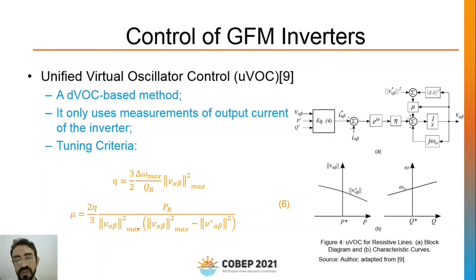We have 3 control gains to define in this control, which are mu, the voltage error gain, eta, the current error gain, and phi, which is defined as the equivalent impedance as seen from the point of coupling of the inverter. At steady state, this control presents this droop relationship, which is nonlinear for active power droop, and linear for reactive power droop, but has a coupling with the voltage. The tuning criteria for this control is also based on steady-state operation points, where the eta gain is defined as a function of the maximum frequency deviation, the maximum voltage deviation, and the rated reactive power. The mu gain is defined in terms of rated active power and maximum voltage deviation, and also the reference voltage.